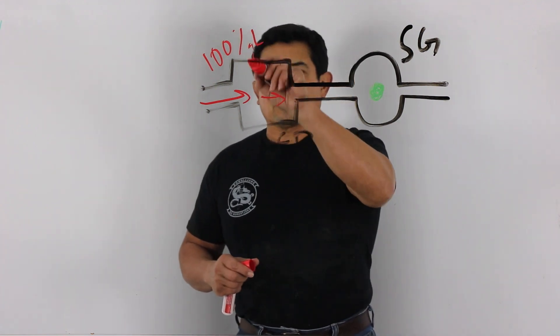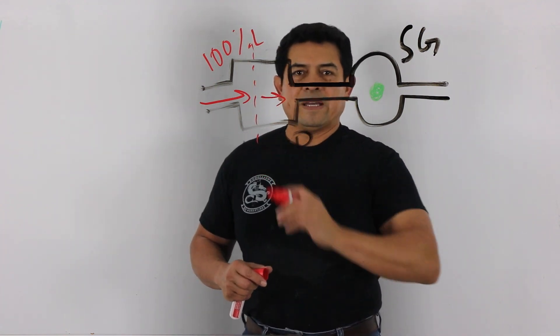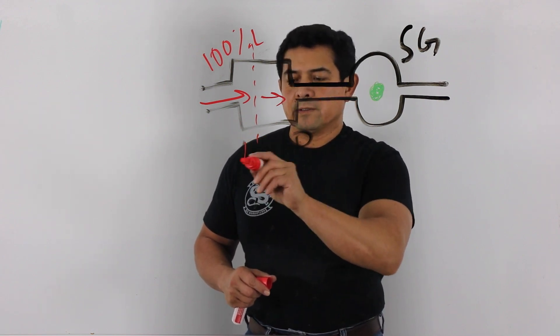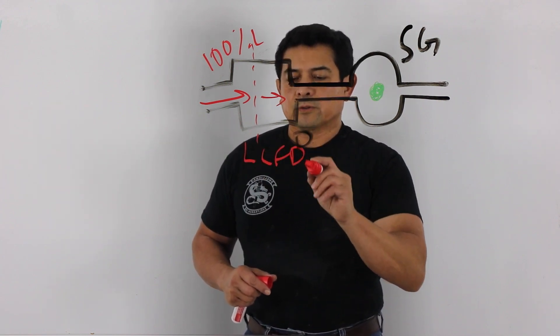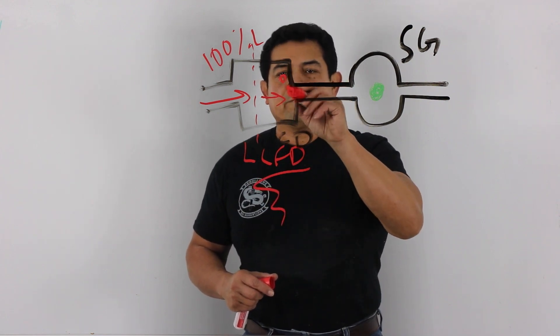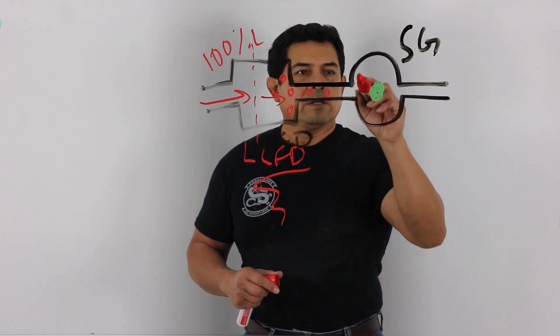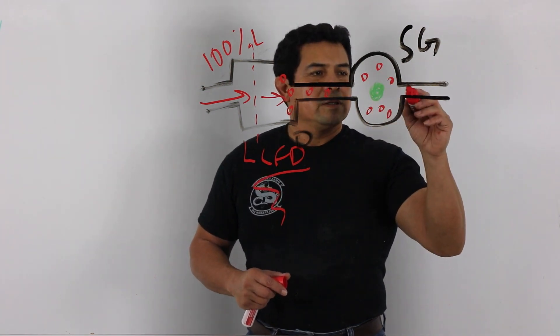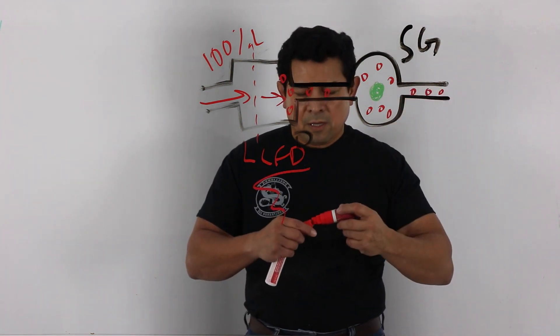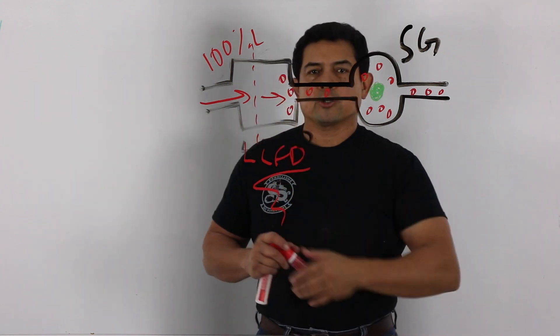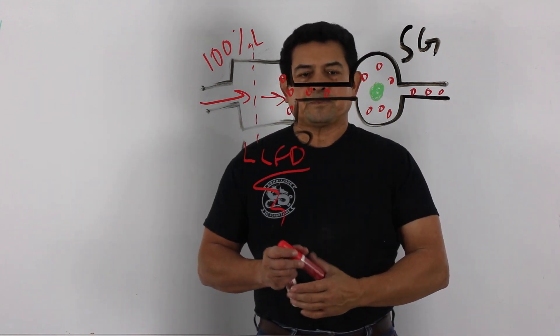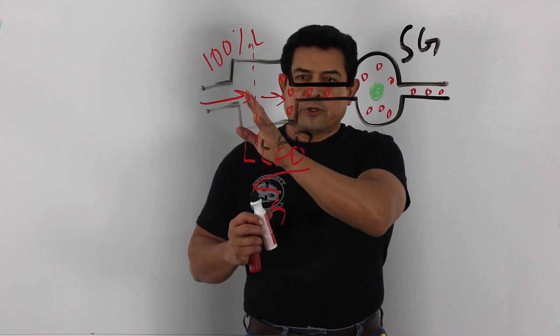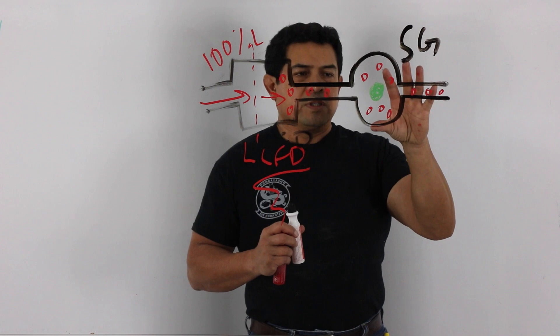Sometimes if the dryer is bad, if the dryer is getting clogged up, this liquid line filter dryer, if this is getting clogged up, then you're going to have flash gas here. You're going to see bubbles in the sight glass. They're going to be traveling through here because you're creating a restriction here. You have a pressure drop right there. So what happens is the refrigerant flashes off, you see bubbles here.